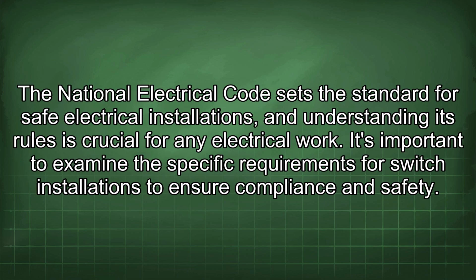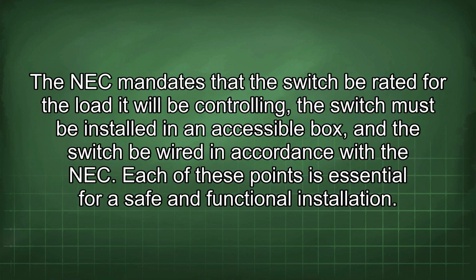The National Electrical Code sets the standard for safe electrical installations, and understanding its rules is crucial for any electrical work. It's important to examine the specific requirements for switch installations to ensure compliance and safety. The NEC mandates that the switch be rated for the load it will be controlling, the switch must be installed in an accessible box, and the switch be wired in accordance with the NEC. Each of these points is essential for a safe and functional installation.